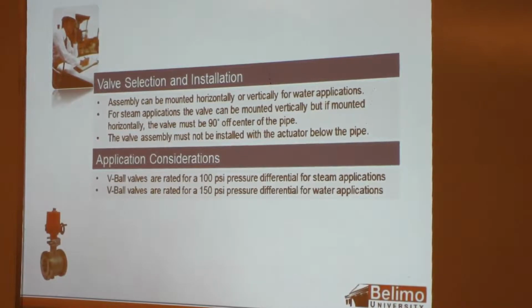Selection and installation, and this really goes for all of our valves. It can be mounted horizontally or vertically for water applications. As I mentioned earlier, we just don't want the actuator mounted below the valve body. For steam applications, vertically or horizontally, but if you're doing it on the horizontal, we suggest that you offset the actuator 45 degrees so you don't have the steam dissipation going up into the actuator.